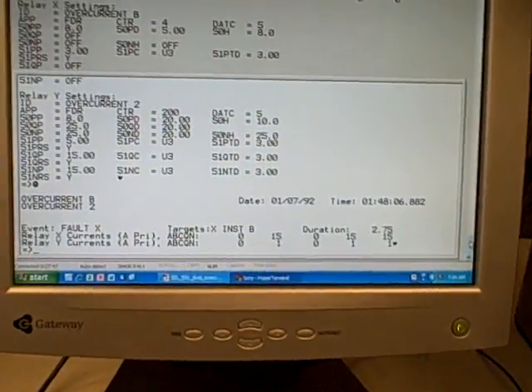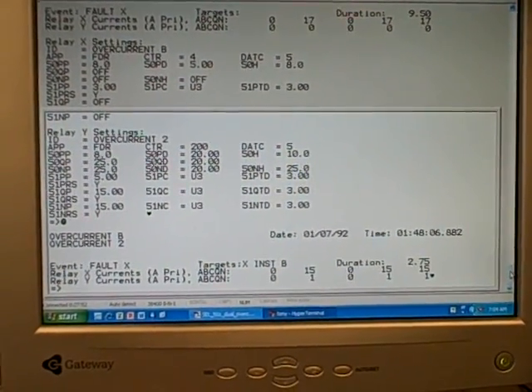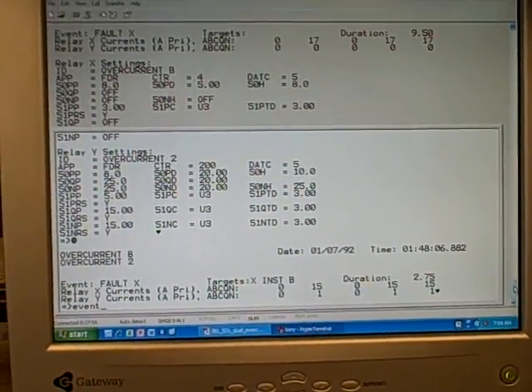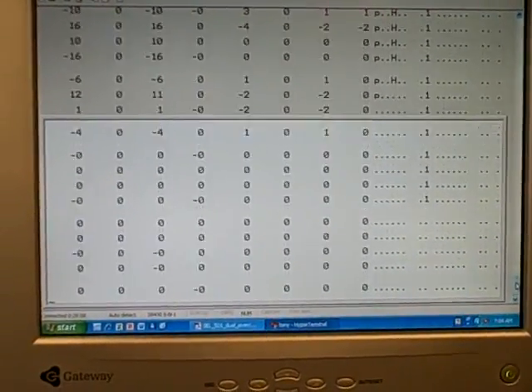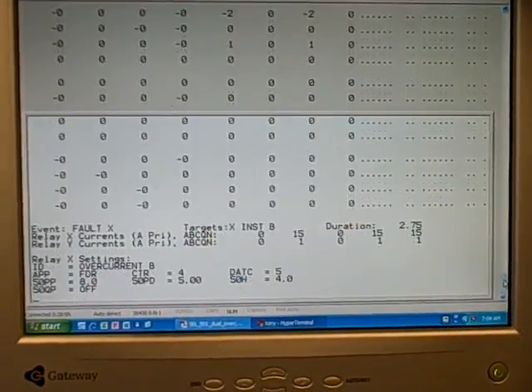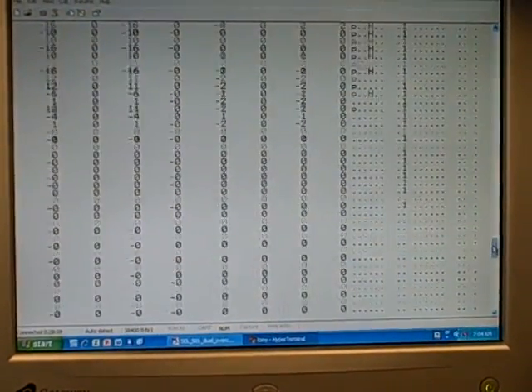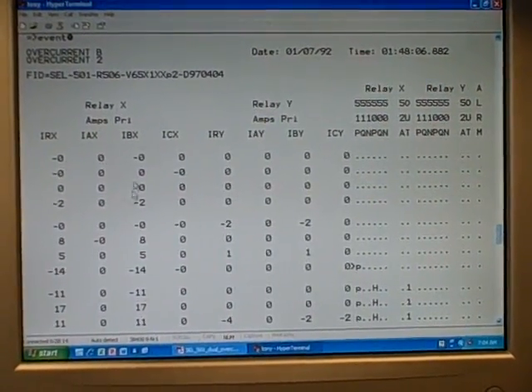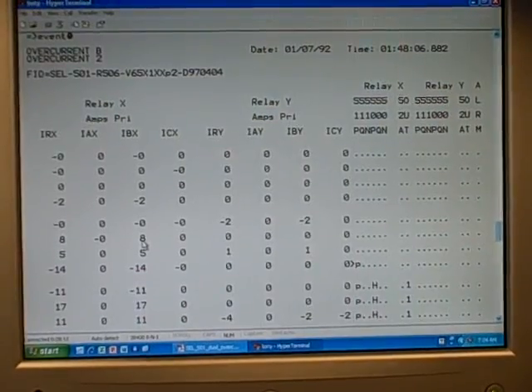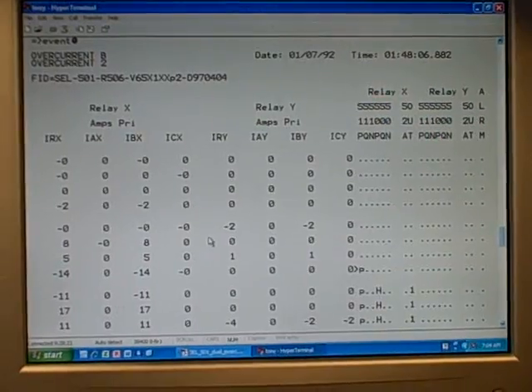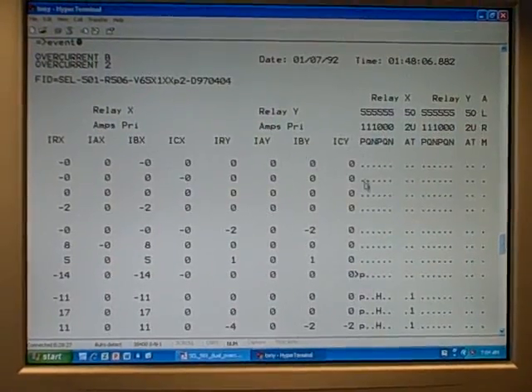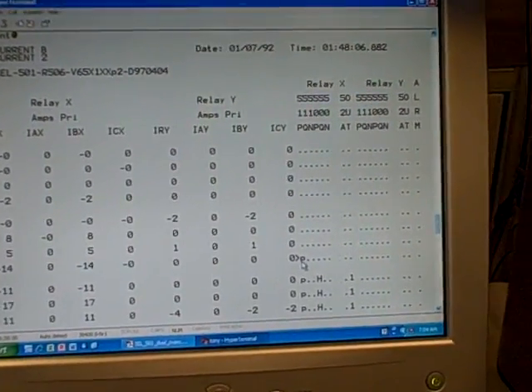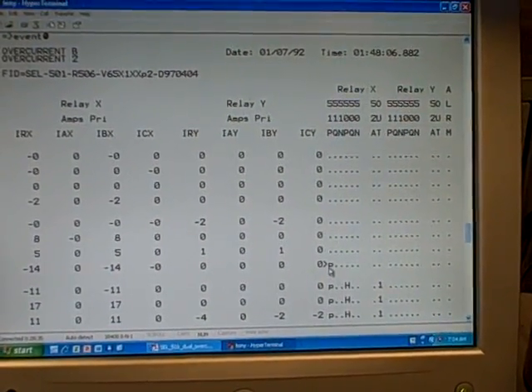Coming over to our display, it did report a fault on over current relay B, duration 2.75 cycles. If I want more event history on this, I can type in the word event. We'll scroll back up to the beginning of this report and analyze it. We see once again relay X, primary amps. The first cycle here is when nothing happened. The second cycle is when the vacuum cleaner was turned on, and we begin to see current being pulled through B phase. We see that we have hit the 51P, the time over current element. It begins to pick up right here. That happens to be set for a pickup value of 3 amps secondary, or 12 amps primary. So it's actually the first one to pick up.